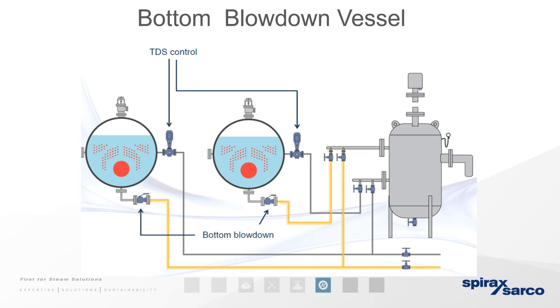So the reason being, we don't want to overfill this tank. We don't want it to leak. If you overfill it, it will hit the overflow and it will go down to drain hotter than intended. So timing of the blowdown is essential.